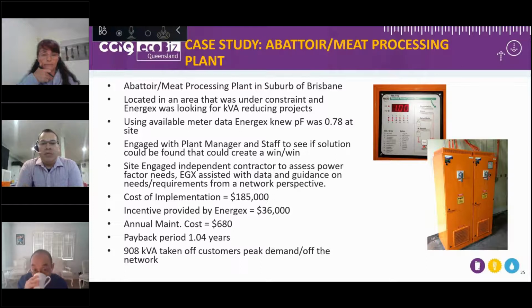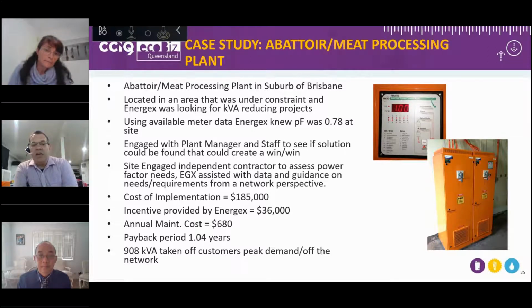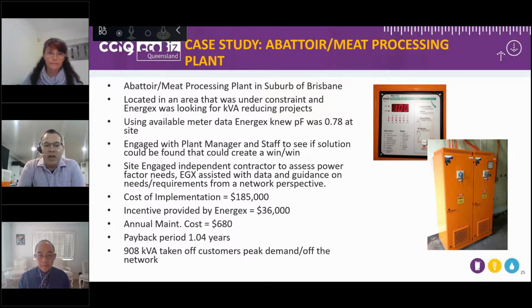So absolutely, this is an abattoir meat processing plant in a suburb of Brisbane, a fairly large operation, and they did identify, and this is going back a few years, this is one that I had my hands on, that they had poor power factor. We also, as Energex, identified that they had poor power factor, and they were being impacted by the kVA charges that had already been implemented at that time. So what I did is I engaged with the plant manager and the staff to see if a solution could be found to create a win-win scenario, a win for the customer and a win for the network.